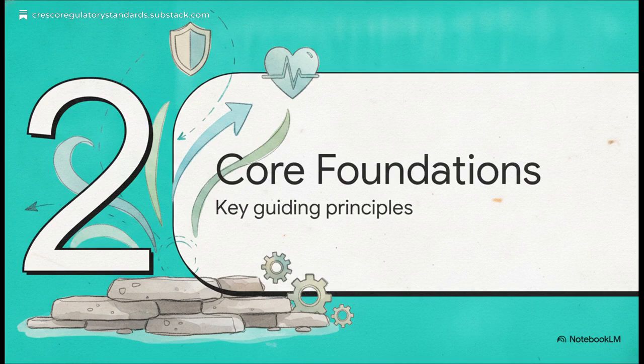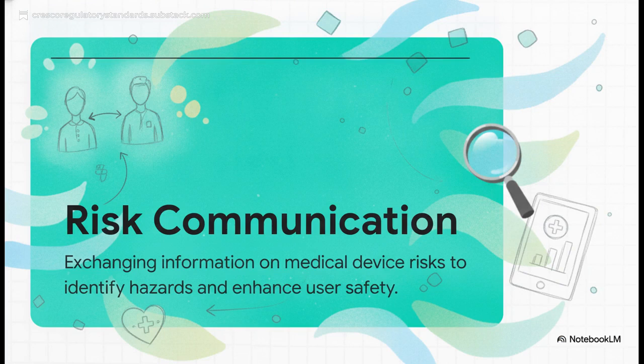Moving right along to Section 2, the core foundations of communication. First off, let's pin down exactly what we mean. Risk communication is the exchange of information related to medical device risks among concerned parties to identify potential hazards, make appropriate decisions, and enhance user safety. The absolutely crucial takeaway here is the human element. This isn't just data pinging from one server to another. It's about empowering patients and healthcare providers, increasing trust, promoting health literacy, and ensuring doctors can accurately balance the potential benefits against the risks for their specific patients.